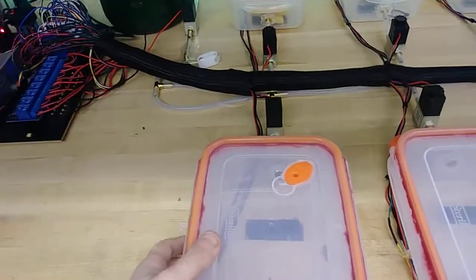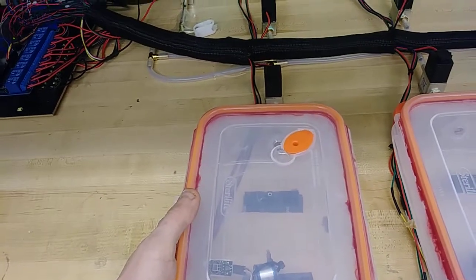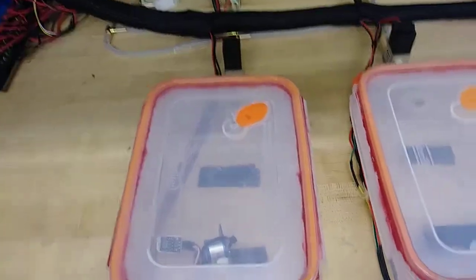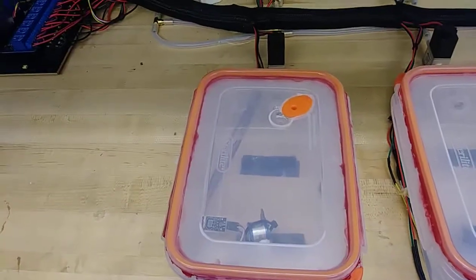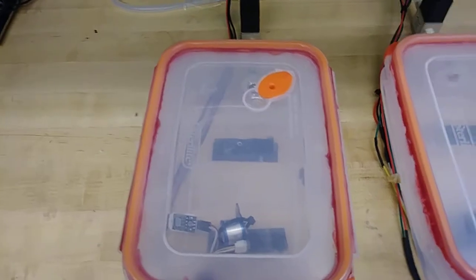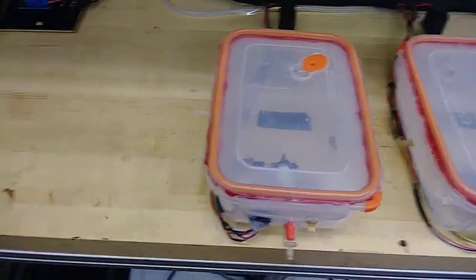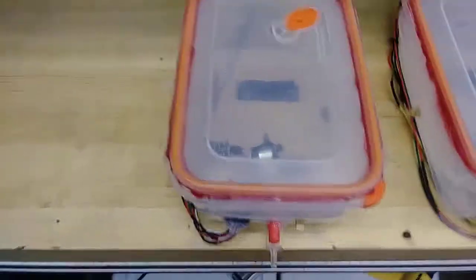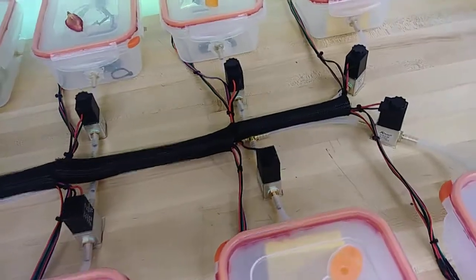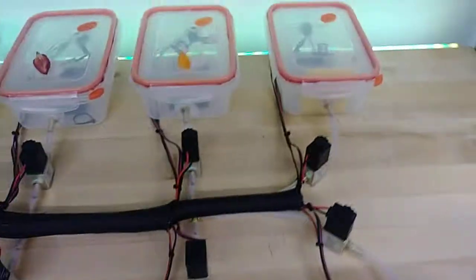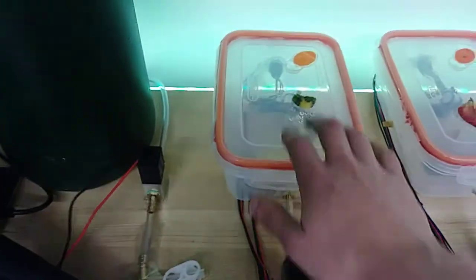But basically how the whole system works is I'm reading O2 inside these compartments, and once the O2 gets above 2.5% overall, I know that the nitrogen content inside here is roughly 97.5. So once it gets over 2.5, I have the solenoid valves open up and we refill the containers with nitrogen down to 1.5 oxygen, which would be about 98.5% nitrogen. So all these containers have roughly 98 to 99% nitrogen inside them, plus humidity, depending on what I have in them, whether it's a sponge or a fruit.